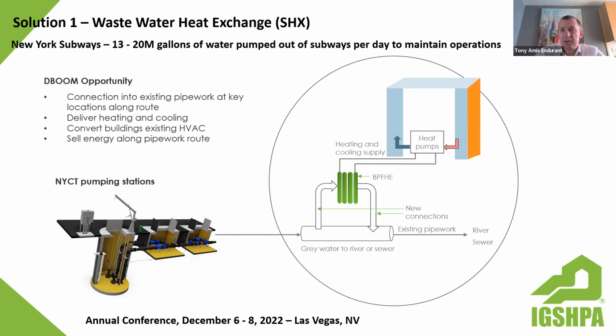This presents another great opportunity - the diagram on the right shows a very simple connection to a plate frame heat exchanger, putting the water back in. The plate frame heat exchanger enables us to exchange a pretty low grade amount of heating and cooling and transfer it into the heat pumps to deliver the heating and cooling necessary to each tower.